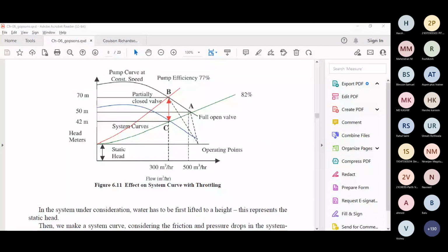Because we never want our pump to operate in shut off, the 20-25% flow rate of the design flow rate will be somewhere around 35 to 40% of the efficiency. Clear? Okay. Yes, sir. Got it, sir. I told that just as an example.